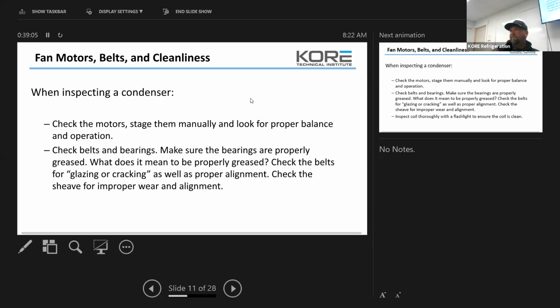So the thing about it is, when you roll an old belt off that's glazed, please inspect the sheaves on the equipment. Make sure that it's not U'd, because the contact on that belt matters. That thing's running an immense amount of RPMs, so you want a good contact point on that sheave. If they're worn out because they've heated up, it's just going to wear out the next belt within a couple of days. So anytime you roll the belt, check that contact point.